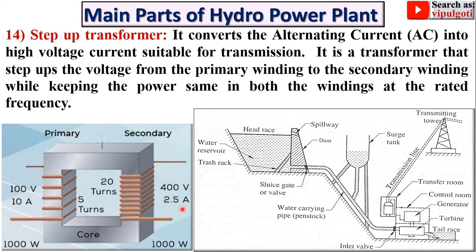At the power station, the step-up transformer is required to increase the voltage. Here you can see the voltage is increased from 100 V to 400 V, and so the current decreases from 10 A to 2.5 A, because power remains constant: 100 × 10 = 1000 W and 400 × 2.5 = 1000 W. It is a transformer that steps up the voltage from primary to secondary winding while keeping the power the same at the rated frequency.